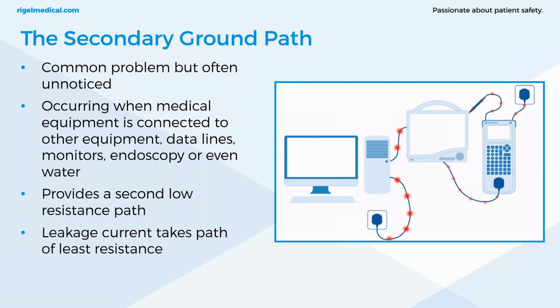Secondary ground path. This is a common problem, but often goes unnoticed. It occurs when medical equipment is connected to other equipment, such as data lines, monitors, endoscopy, or even water. Now, the image on the right represents an example of a secondary ground connection, and this is via a data cable to the PC. Most of the current is taking the path of least resistance. This is grounded as well, so you're likely to get a value that's below 1 ohm.